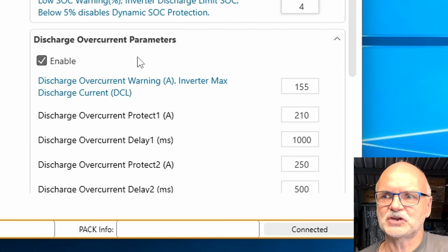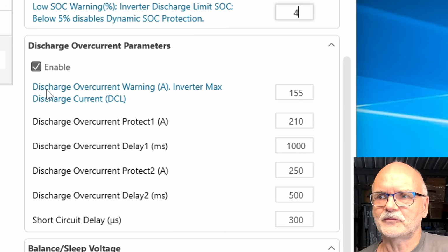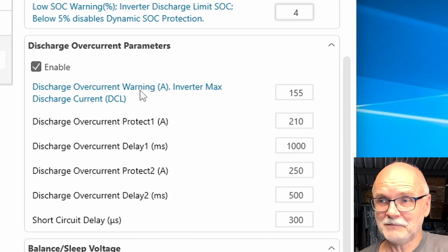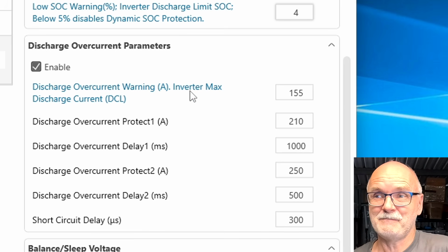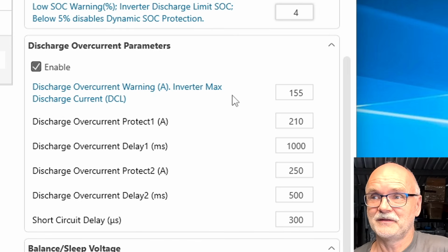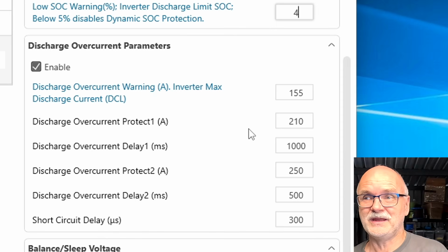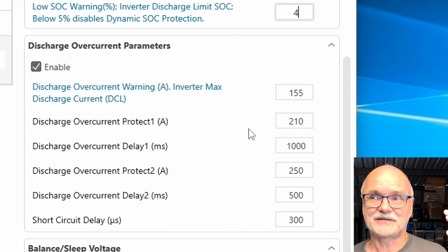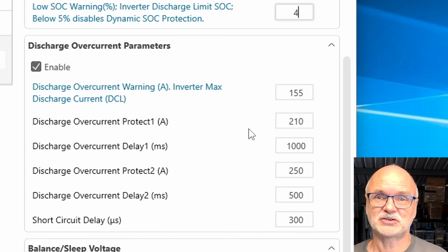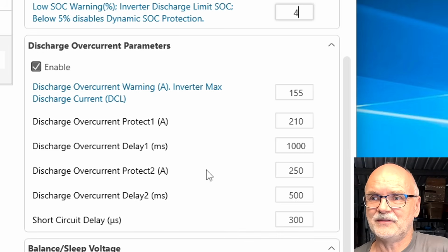Okay, then we've got the discharge overcurrent parameters. So we've got the discharge overcurrent warning, and this is also your inverter maximum discharge current, 155 amps. But we've got the protection of 210 amps again. Here's the warning, and the DCL is decoupled from your protection parameter - very good, I like it. And then we've got a delay, and another overcurrent protection of 250 amps.